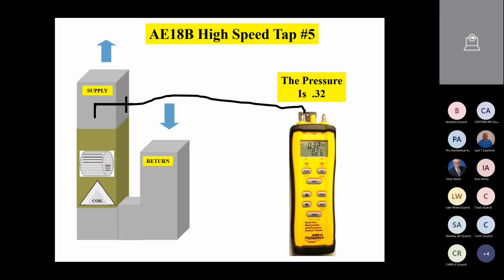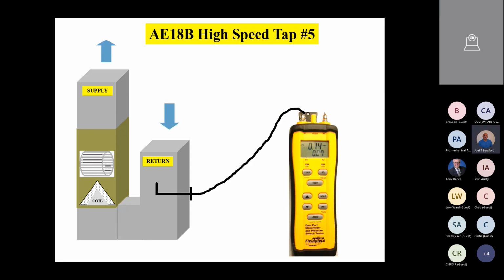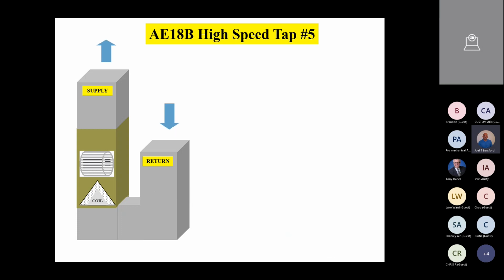0.32. And then our second reading on our return is a 0.14. So we have an AE 18B high speed tap number 5, 0.14 on the return static. And so we add those values together. We have a 0.32 plus a 0.14 that gives the total static of a 0.46.